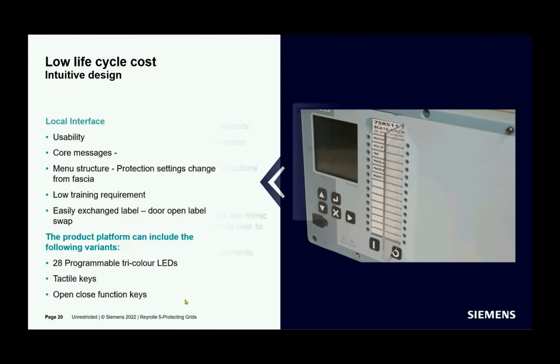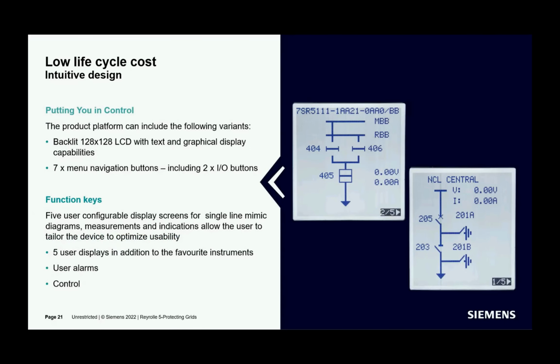Now, all 7SR5 relays are equipped with a backlit 128 cross 128 LCD with text and single line diagram display capability. Via Reydisp Manager 2, it is possible to add 5 user configurable display screens for single line diagrams, all analog measurements, and all defined alarms and indications. So you can see the single line diagram in the first screen and measurements in the second screen, and some pickups or trips or any other indication you decide in the following screens.